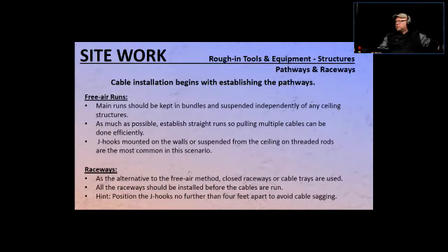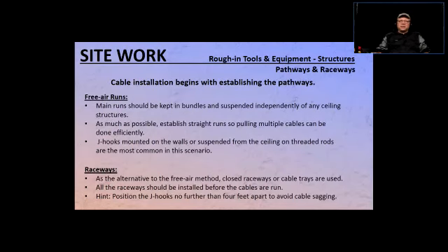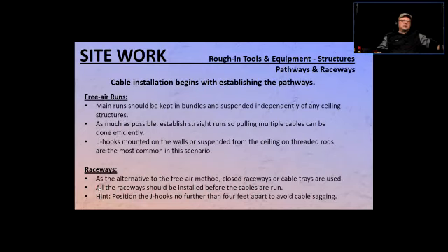I'll talk about J-hooks and threaded rods a bit more. All raceways should be installed before the cables are run — that's a big part of the job. Sometimes on a bigger project it will take you a week or two just to install the J-hooks, cable trays, and things like that.